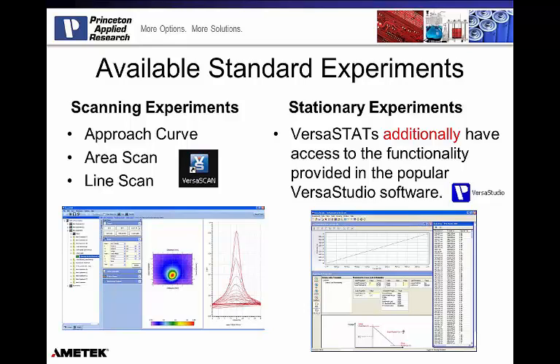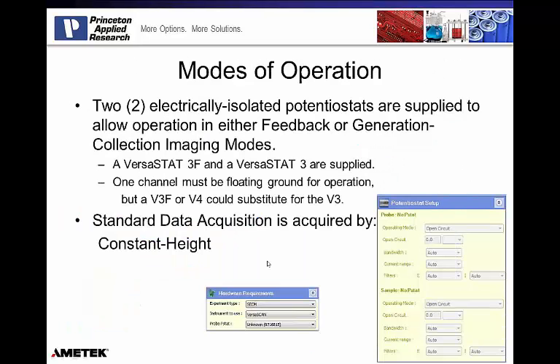But we're also capable of doing dynamic signal experiments. These are experiments like cyclic voltammetry or an impedance experiment, where the signal controlled by the potentiostat is much more complicated. It's either a scan or a sweep, a ramp, or an AC measurement in those two examples I just gave. But in doing those, we typically would hold the probe in a fixed position. So the parameter being changed is the voltage, not the position in those types of stationary experiments.